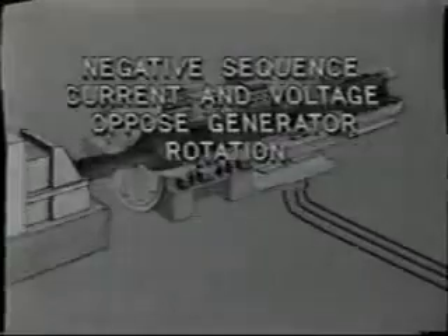But the negative sequence relay also has a primary function. That is to prevent overheating of the generator rotor in the case of prolonged out-of-balance operation. We can think of the effect of negative sequence current and voltage as opposing generator rotation, and the consequent braking effect causes overheating of the rotor. This would occur if the load demand on each phase is significantly unbalanced. A typical example of this occurs where an industrial generator may be feeding, say, an electrolytic furnace or other unbalanced loads or lines. The generator designer specifies the negative sequence limit for each particular generator.